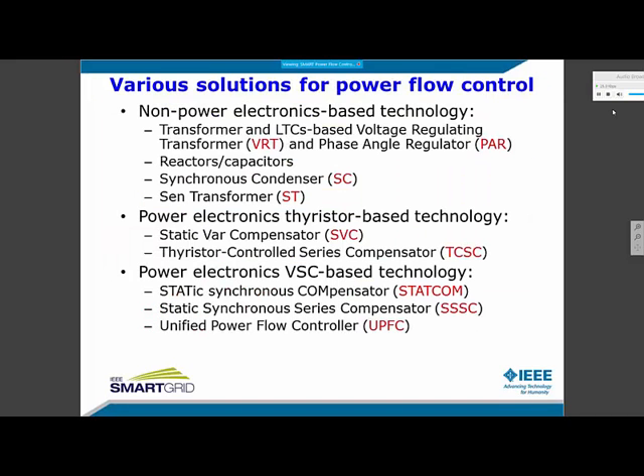Various solutions are presented here. In the non-power electronics version of the solution, there are voltage regulating transformers, phase angle regulators, reactors, capacitors, synchronous condensers, and transformers. The power electronics thyristor-based technology, in which a thyristor switch is used, is found in the static VAR compensator and the thyristor controlled series capacitor, TCSC. However, the inverter uses a controlled switch that can be turned on and off when desired, and it's used in STATCOM for voltage control, SSSC for the line reactance control, and the unified power flow controller, which is an impedance control.